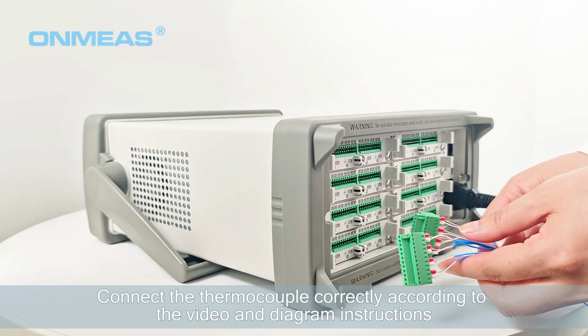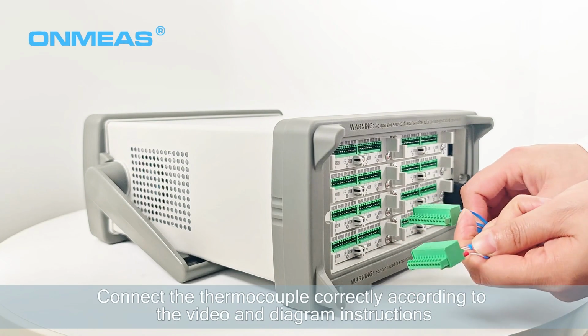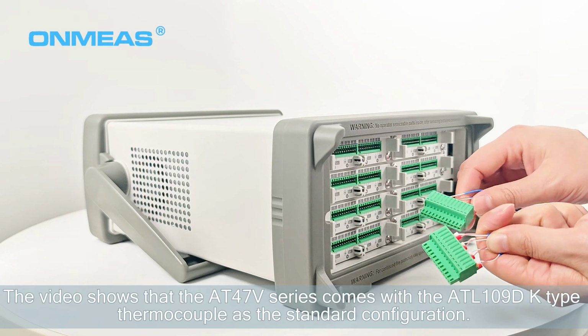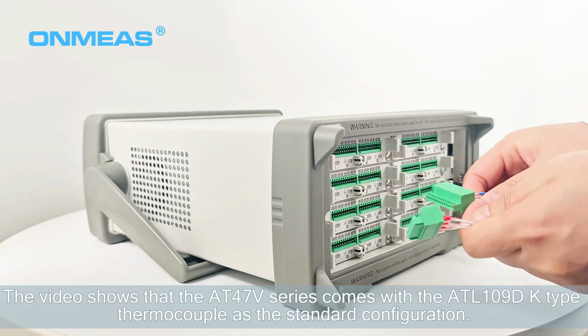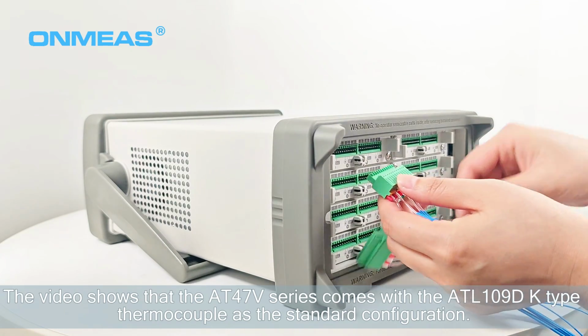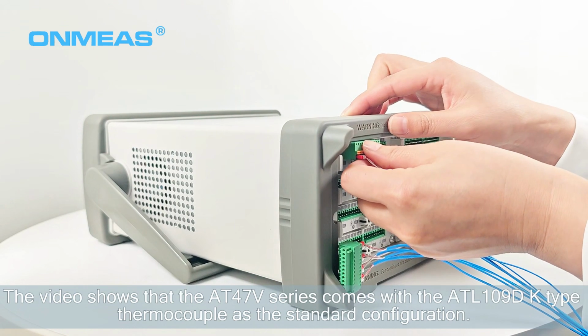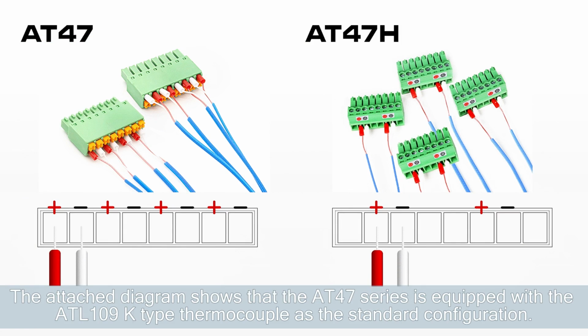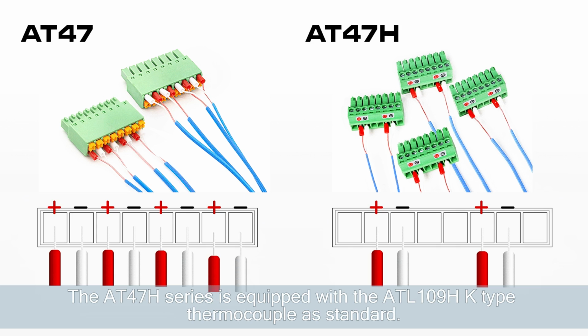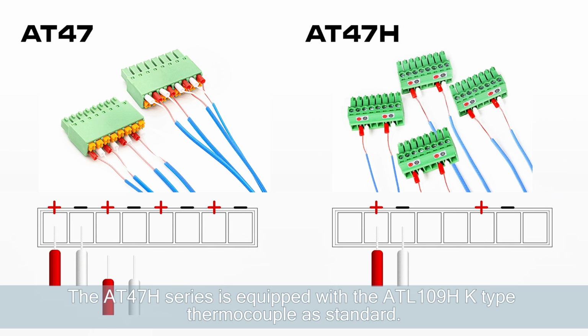Connect the thermocouple correctly according to the video and diagram instructions. The video shows that the AT47V series comes with the ATL109D K type thermocouple as the standard configuration. The attached diagram shows that the AT47 series is equipped with the ATL109K type thermocouple as standard. The AT47H series is equipped with the ATL109H K type thermocouple as standard.